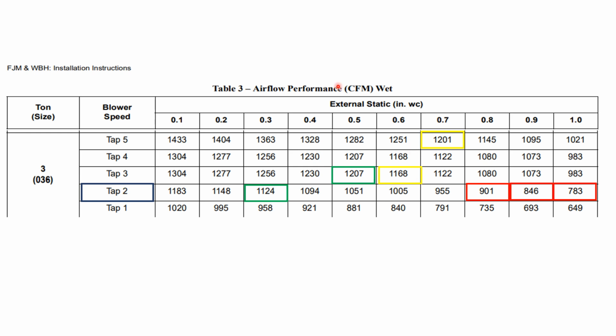Well, that's what this is. We want a healthy static pressure range for your unit. And ICP says no more than 0.5. We optimally want to operate right here between 0.3 and 0.4. This is our optimum range. This is where we really want to operate in this area.